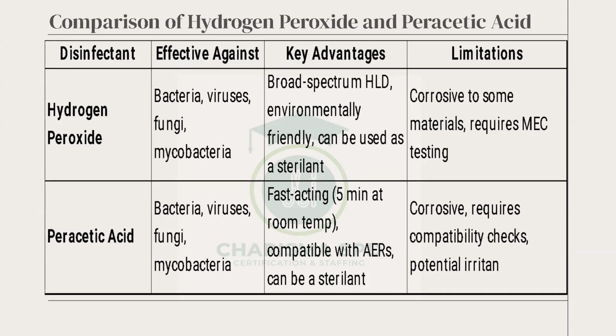Then when it comes to limitations, well, corrosive, but that applies to both. Corrosive to some materials, requires MEC testing. Corrosive requires compatibility checks. With the peracetic acid also, there is MEC checking. We check the MEC in the machine in the AER. You just lift there is a lever or a door, you just lift it and then you get the chemical. So the MEC is also checked. Anyway, just to let you know if you don't see it over there. All right. Next slide, please.